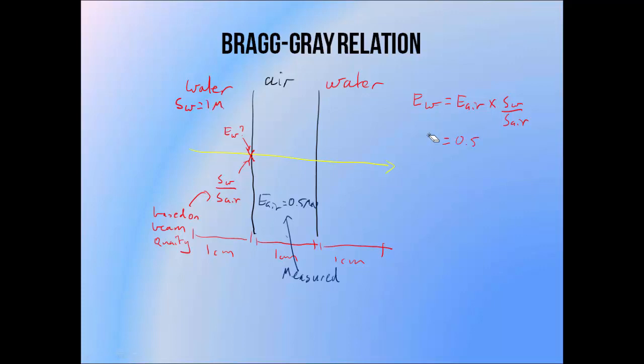If the electron stopping power in water was 1 MeV per centimetre and the stopping power in air was 0.5 MeV per centimetre, the amount of energy deposited in water would be equal to the 0.5 MeV measured in our air volume, multiplied by 1 over 0.5, which gives us a value of 1 MeV absorbed in the water. The first Bragg-Gray condition has to do with the applicability of the stopping power ratio. Stopping powers vary with electron energy, so if the secondary electrons crossing the ion chamber don't change energy very much, then the stopping power ratio will be the same everywhere inside the air volume. But if the electrons lose a significant amount of energy as they cross the air volume, we can't just apply this simple stopping power ratio to get our dose to water.